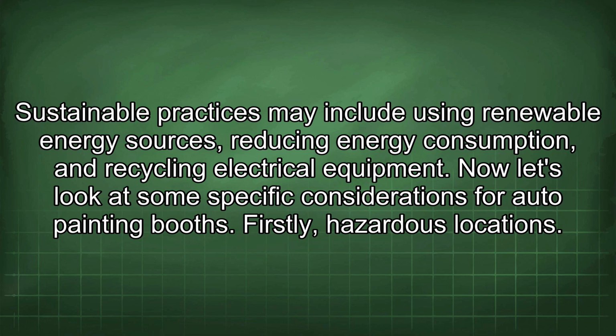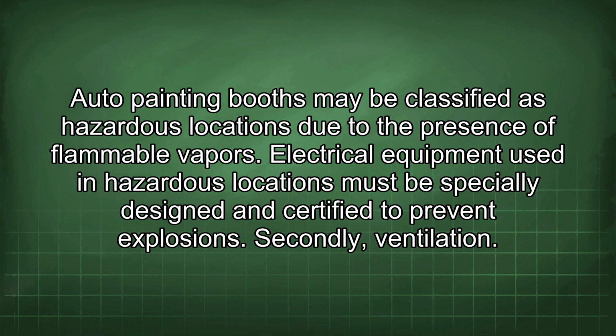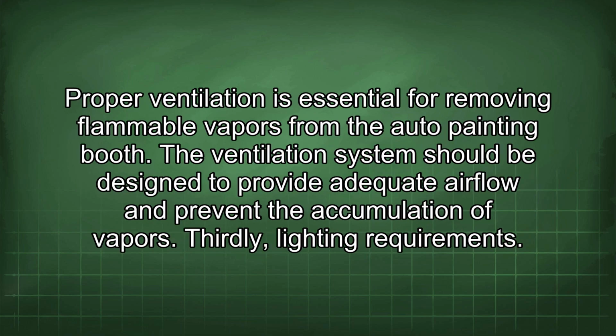Firstly, hazardous locations. Auto painting booths may be classified as hazardous locations due to the presence of flammable vapors. Electrical equipment used in hazardous locations must be specially designed and certified to prevent explosions. Secondly, ventilation. Proper ventilation is essential for removing flammable vapors from the auto painting booth. The ventilation system should be designed to provide adequate airflow and prevent the accumulation of vapors.